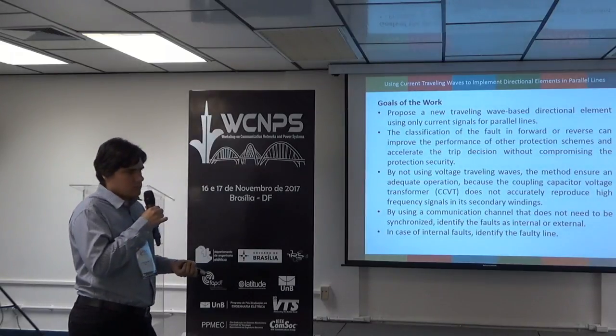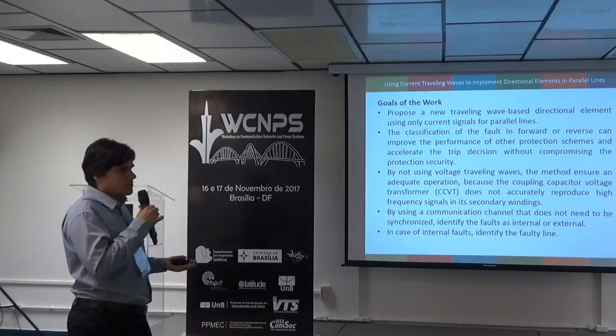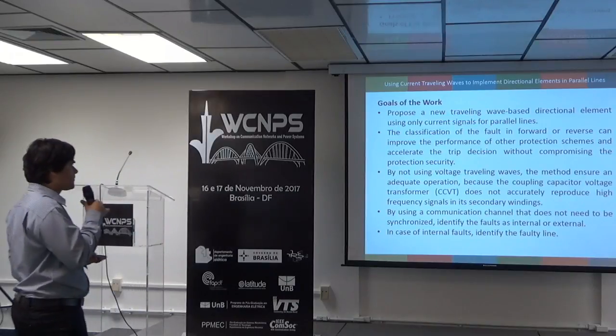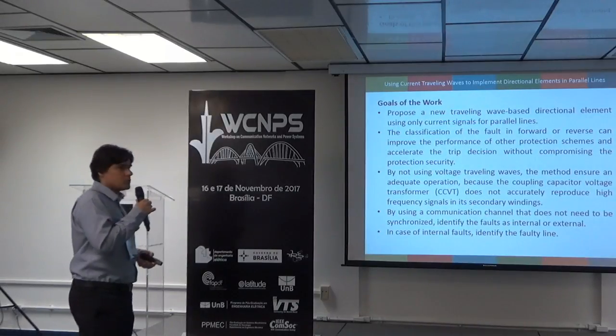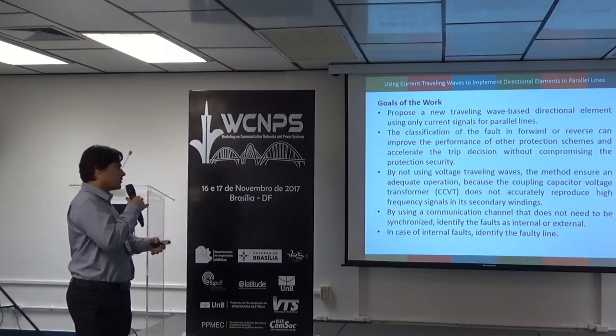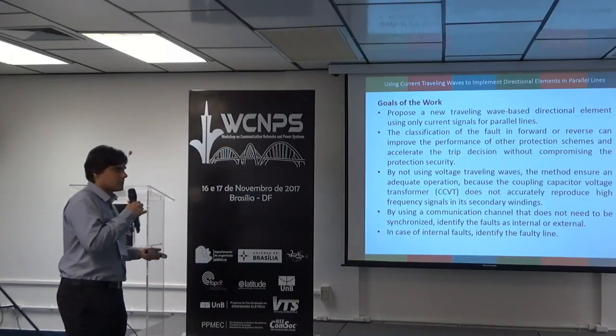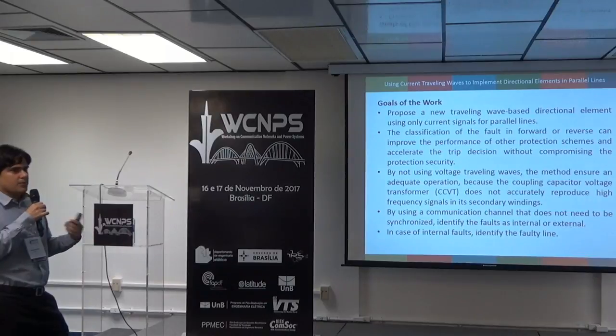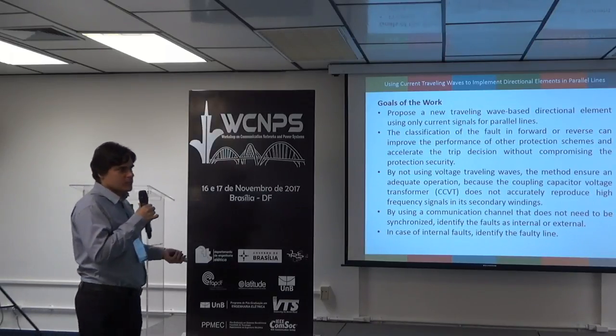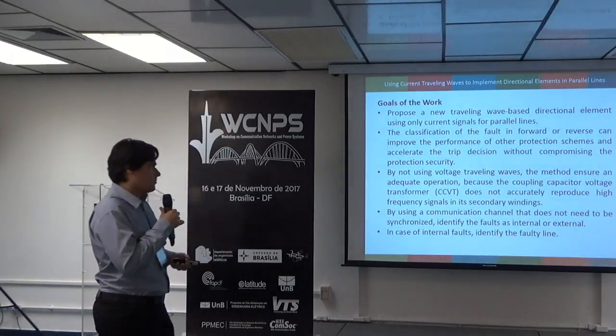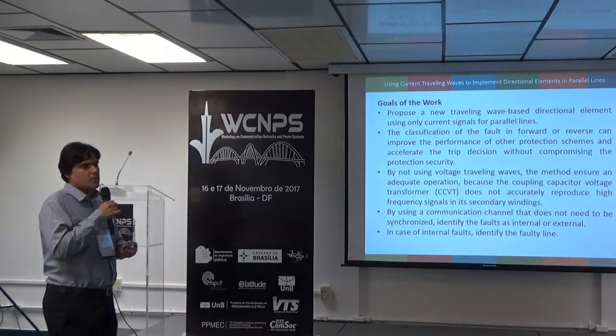If you have a double circuit parallel line topology, we can use the current traveling waves that come from both lines. The classification of the fault as forward or reverse can improve the performance of other protection schemes and accelerate the trip decision without compromising protection security. We could use phasors, but with ultra high speed protection, there is not enough time to correctly estimate the phasor. Because of that, directional elements using traveling waves have been proposed.